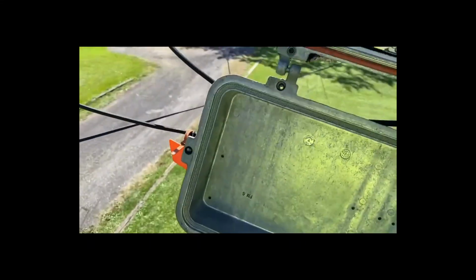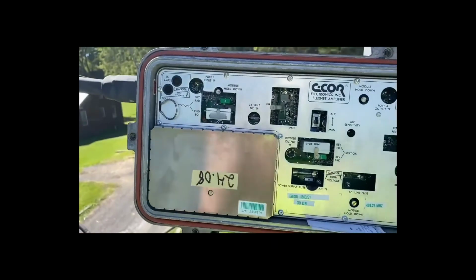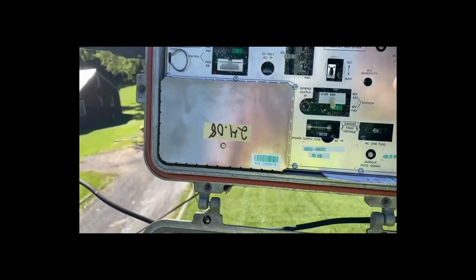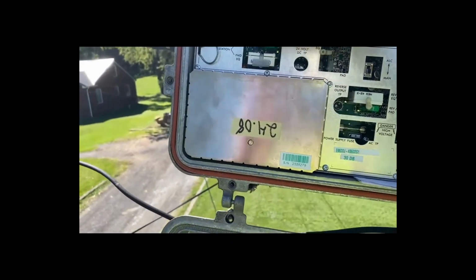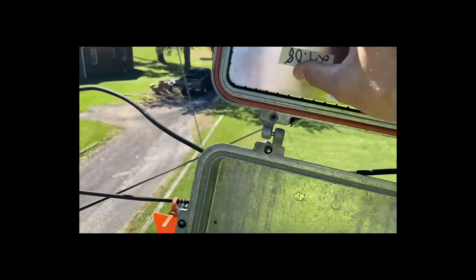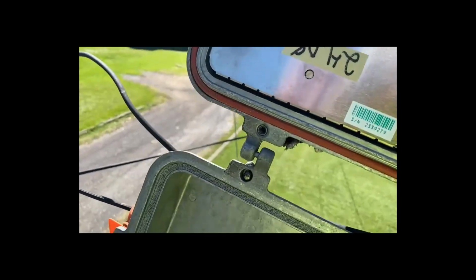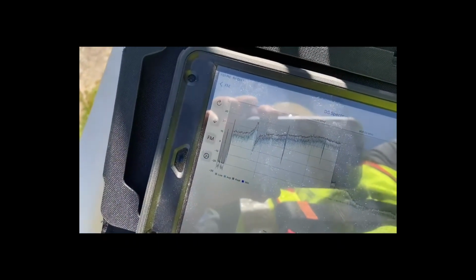It's still there. This is our guy, a 700 series C-COR line extender. Looks like all the module retainer screws are tight. So let's check the input and see if that guy's there on the input. I suspect it's not, but we'll find out.